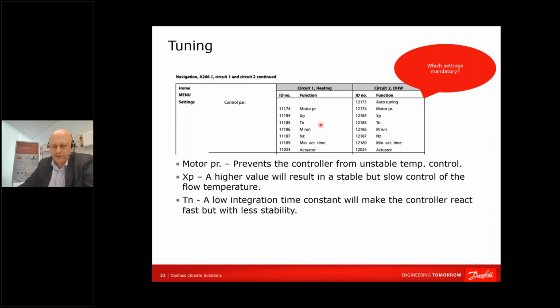Yep. So integration time is, as I just explained with the flushing of the water in a toilet, that is how fast your valve is opened. So you have to multiply valve stroke by actuator speed. If we have a 5 millimeter stroke and 3 seconds per 1 millimeter of speed, then 5 times 3 equals 15 seconds.